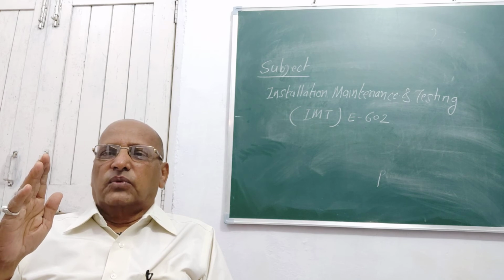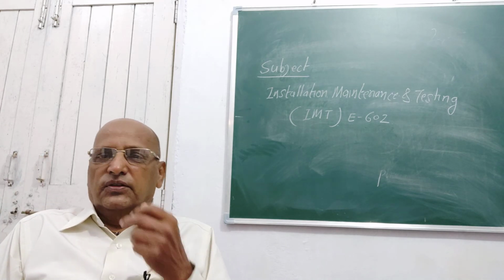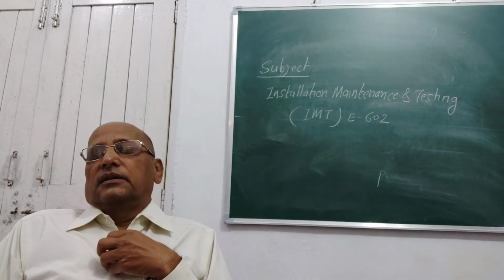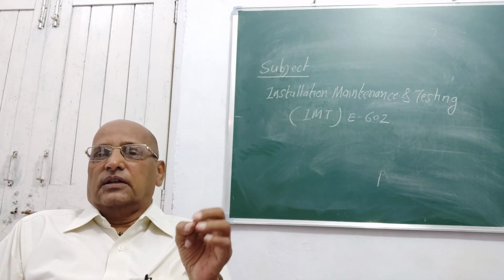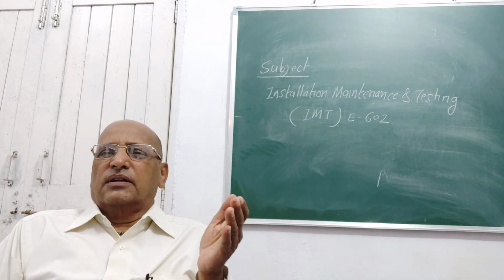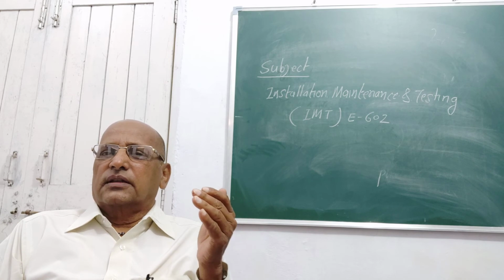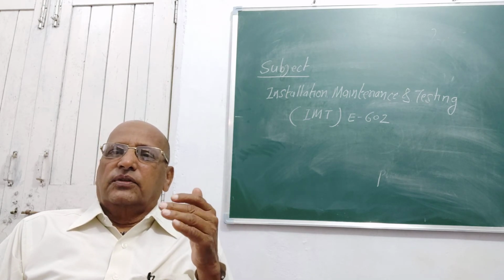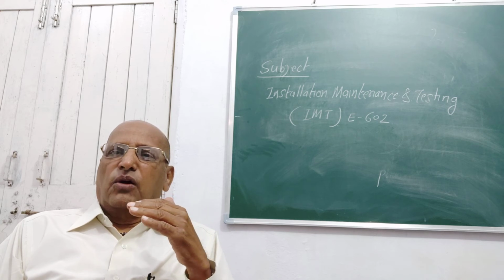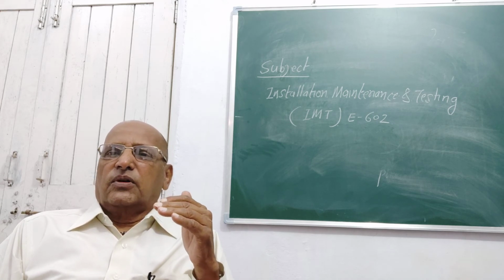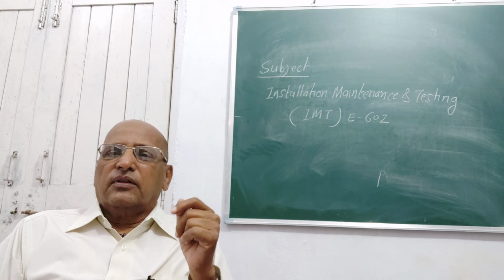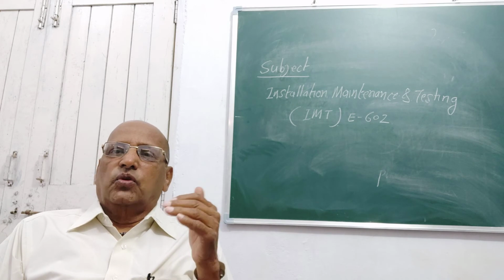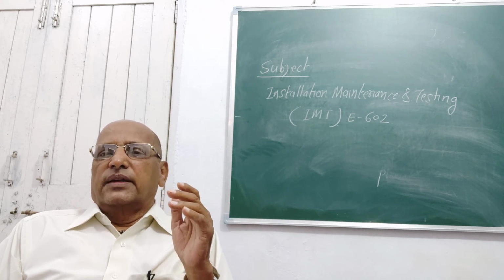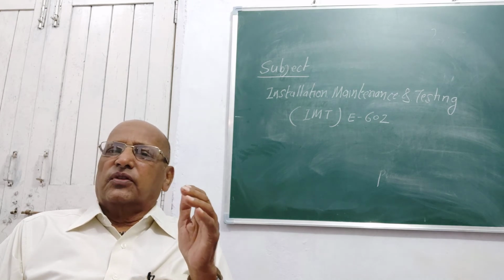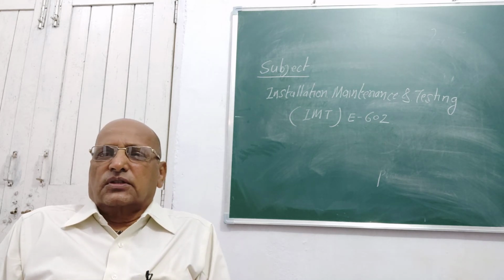Whenever it is not possible to erect a pole at the site, then we can go for the foundation mounted type of structure. Just near the bank of a river, for example, it is not possible to install a pole. So in that case we prepare a foundation with concrete, and then the transformer can be put on that. So it depends on the site situation whether you have to use pole mounted or foundation mounted. In maximum, 90% of cases, we go for pole mounted substations in the distribution system.